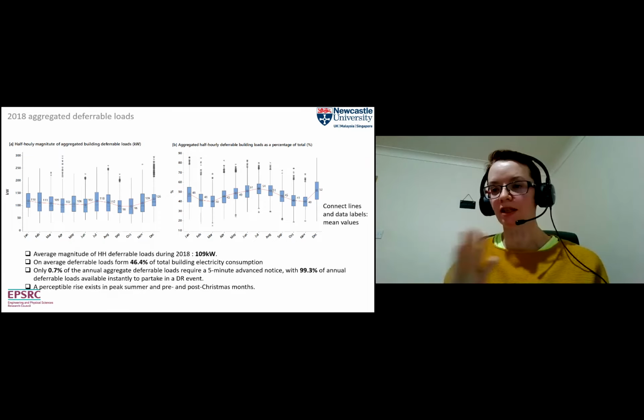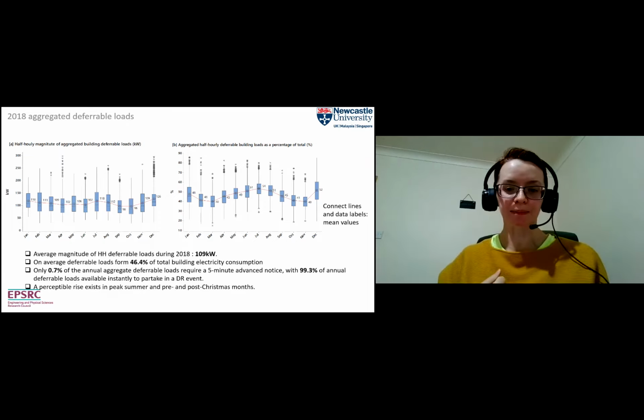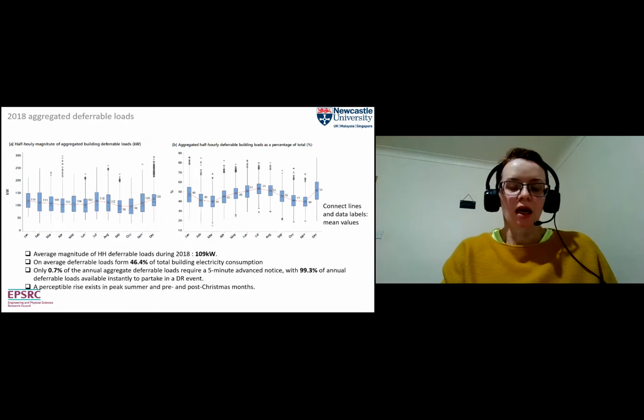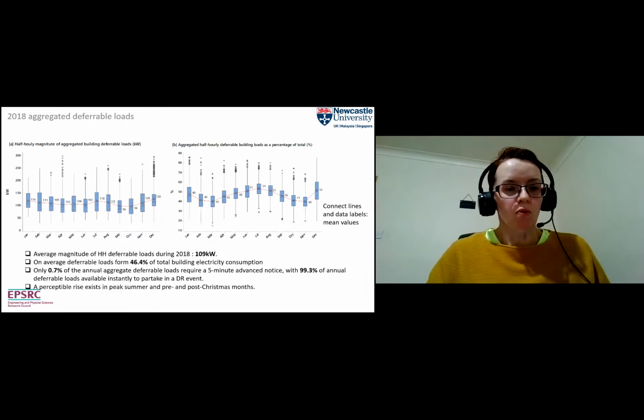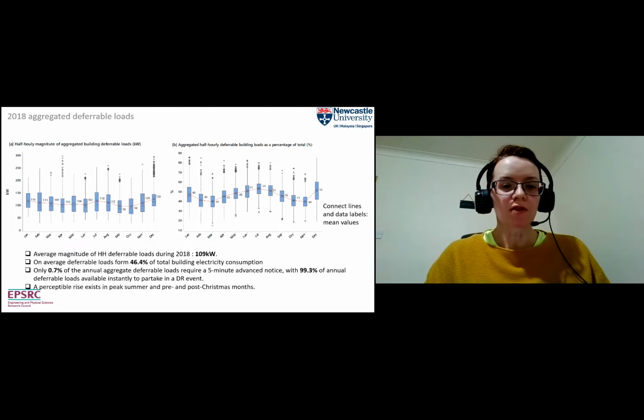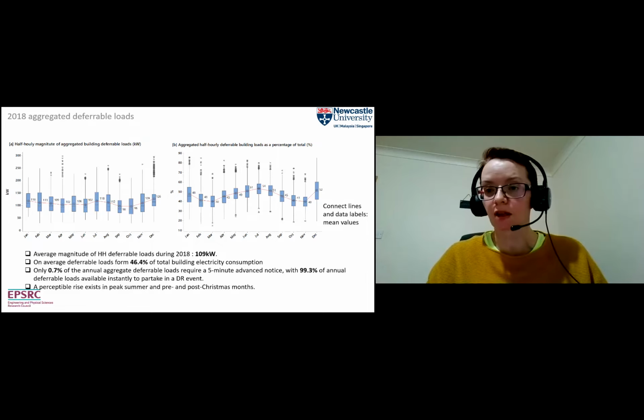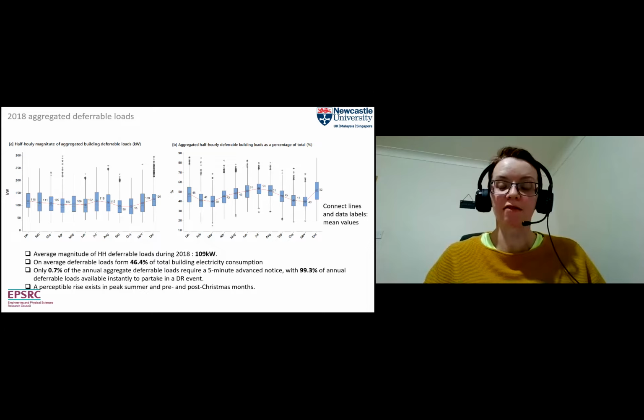Most things could turn off instantaneously. So what this means in terms of the amount of load we could offer is that it's seasonal, but certainly not insignificant. It's not like demand response for this commercial building is 10% of its load. No, it's more like 45 to 46%, and that varies throughout the year.